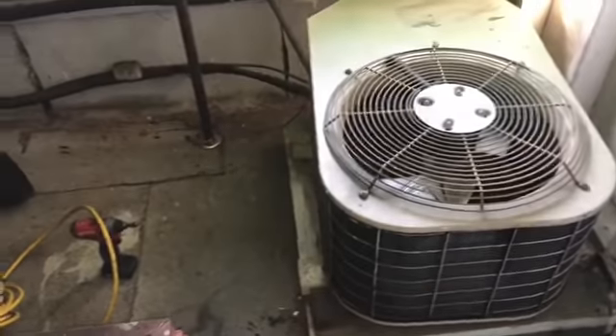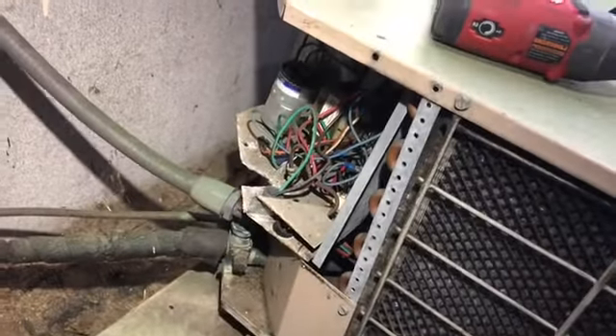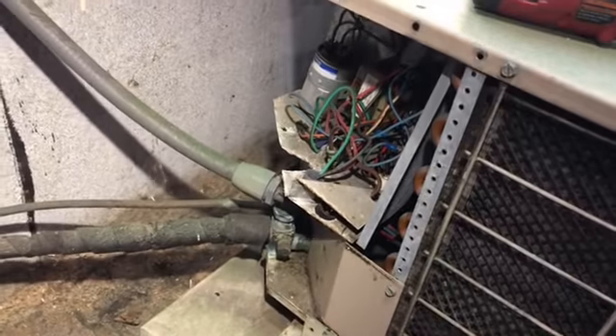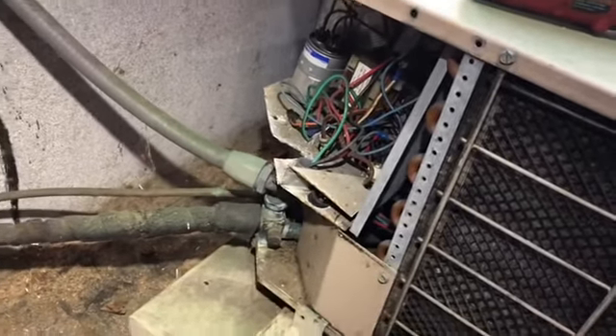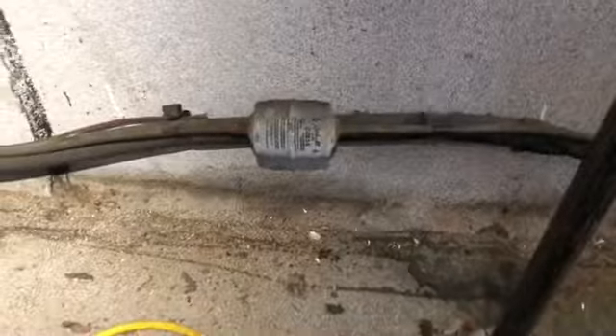There's one refrigeration unit out here. So this is coming out. They had the transformer right there — they had the thermostat running off of it. There's a hard start in there too. They had the transformer running off low voltage. Maybe it was installed by an air conditioning guy — who knows? That's what it looks like. It looks more like an air conditioner job than a walk-in box.